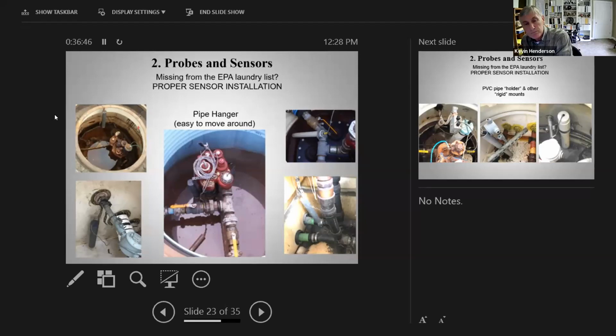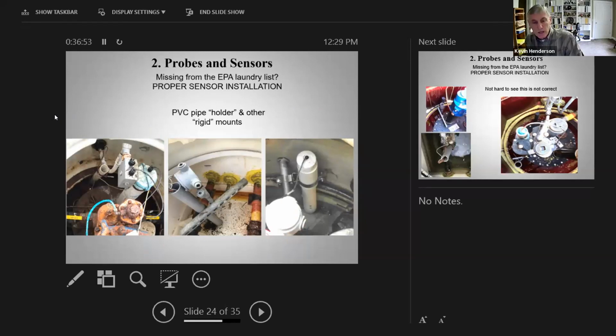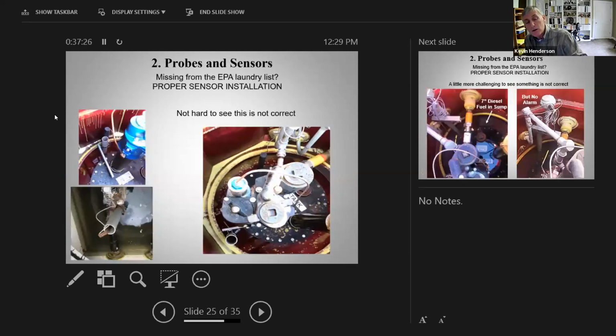So in an effort to try to make this better, we've had people do something like this, if you will. They will take some electrical conduit or something like that, and you'll see a lot of people put it in a piece of 1.5 or 2-inch PVC. And that's what you're seeing in these 2 pictures here, the one on the left and the middle. A piece of PVC pipe that's mounted to some J-channel, and the sensor is simply dropped down into the pipe itself. They attempt to keep it vertical. The thing about this is, again, it's not hard to figure out. You can look at the bottom left picture and you see what they did. There's water in the sump. So instead of the sensor sitting at the bottom of the sump again, you pick it up, take that wire hanger, bend it over the lip of the pipe that it's in, presto bingo, you're out of alarm, problem fixed, right?